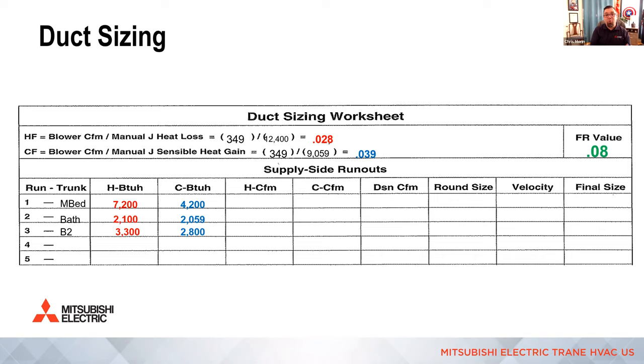But as an example here, we would multiply 7,200 for the master bedroom in heating times 0.028 for the heating factor to come up with heating CFM. In this example, it was 201.